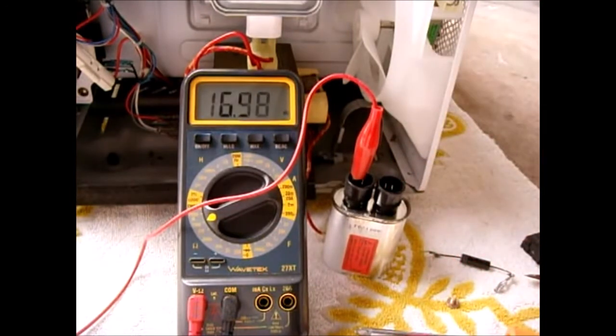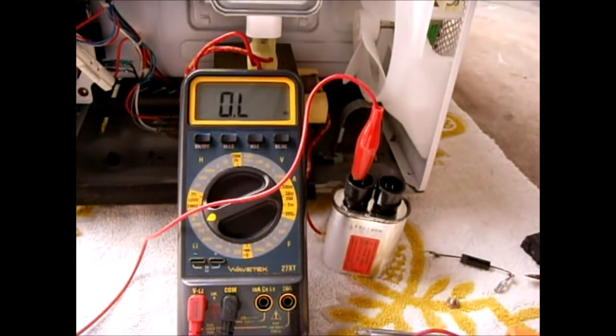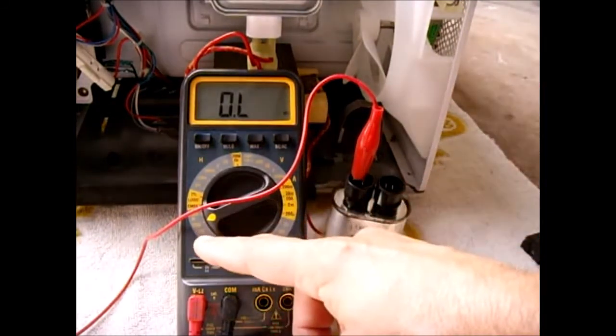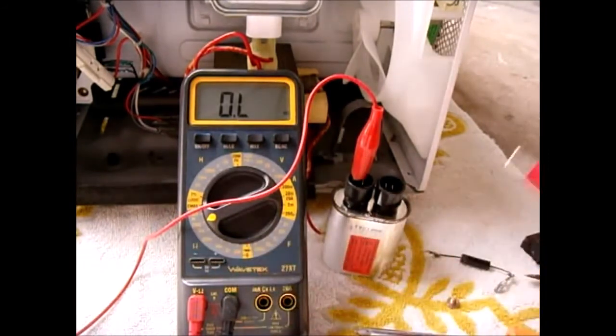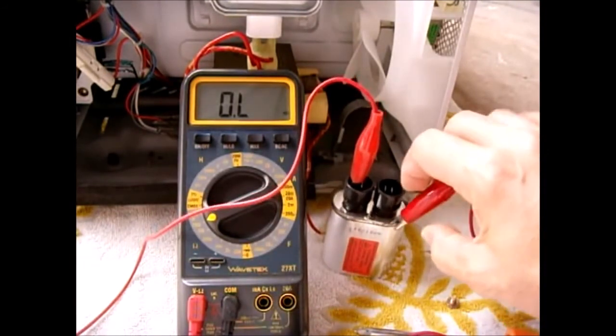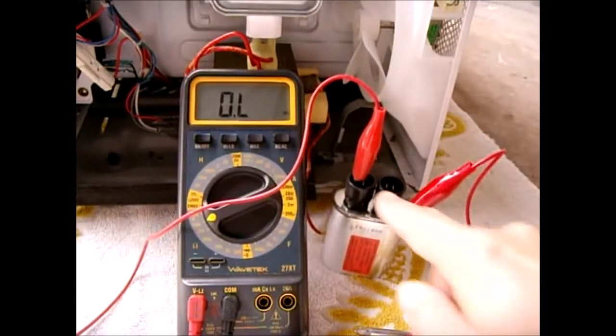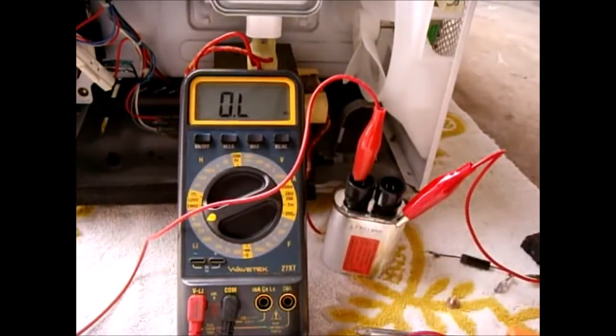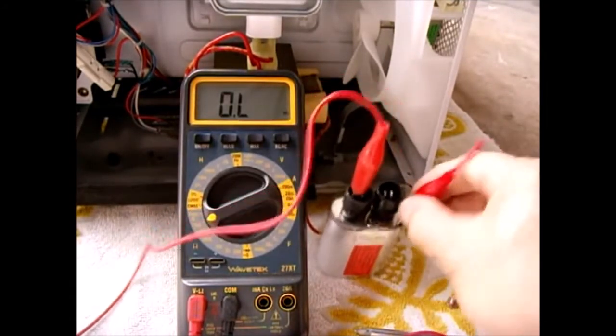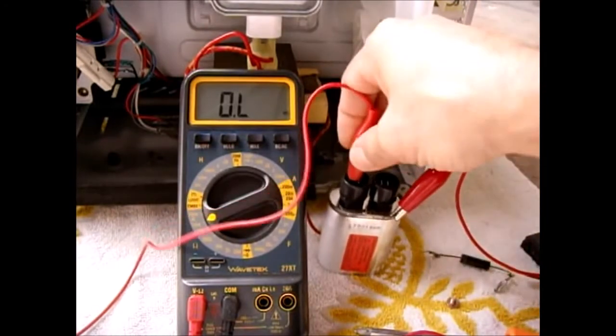The next test to verify if this is any good: leave one terminal connected and take the other terminal on the 20 meg setting, or 200 if you have it, and connect it to the can. You want to make sure there's no connection between the terminal and the can.